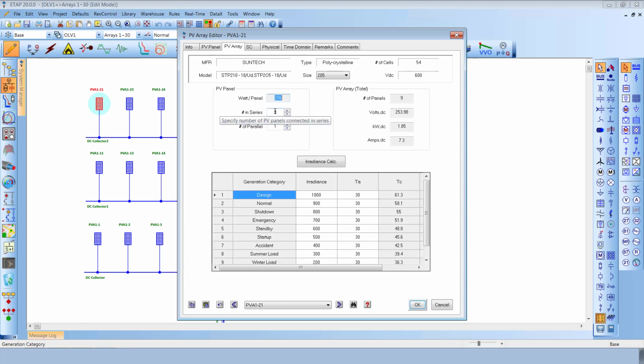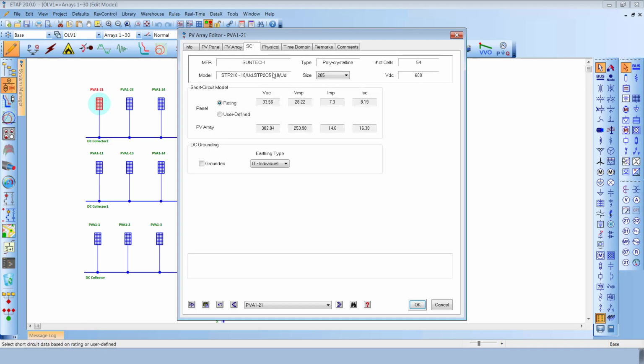It is important to build your panel based on adding PV arrays in series or in parallel. So the number of PV panels added in series directly impacts the voltage of this particular PV panel. In other words, adding PV panels in series increases the voltage of this PV panel, and the best practice is to make sure the voltage from the PV array in total matches the nominal voltage of the collector bus that it's connected to. Adding PV panels in parallel increases the current contribution from the PV arrays, and it can be summarized in the corresponding short circuit page of the same panel.